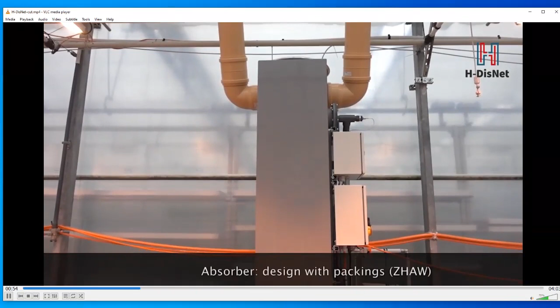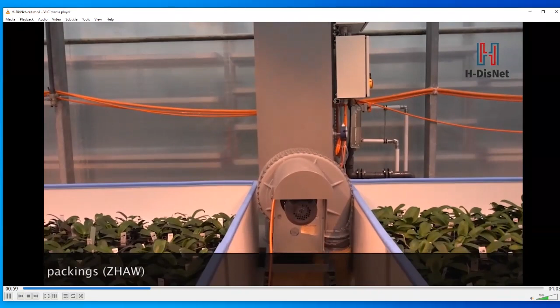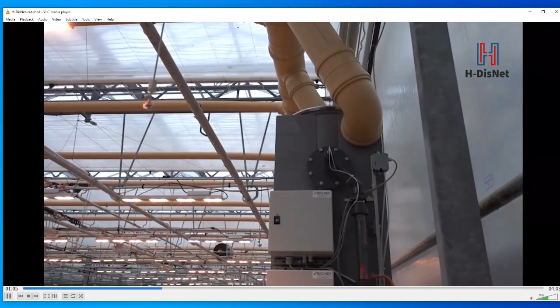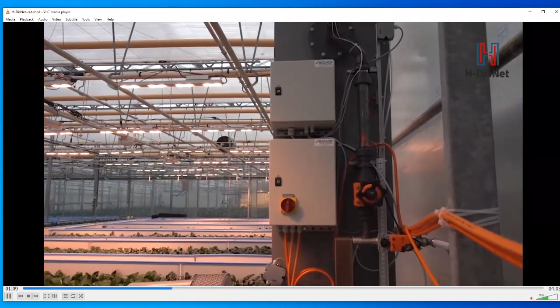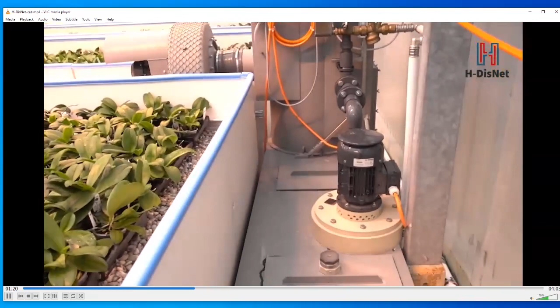This is the absorber. We take the air from these orange ducts - this is the absorber, and the fan is integrated into the construction of the absorber. This part, difficult to see, is the pipe for the salt solution, and this orange is the valve for the salt solution. Here is the sump where the pump for the salt solution is integrated.